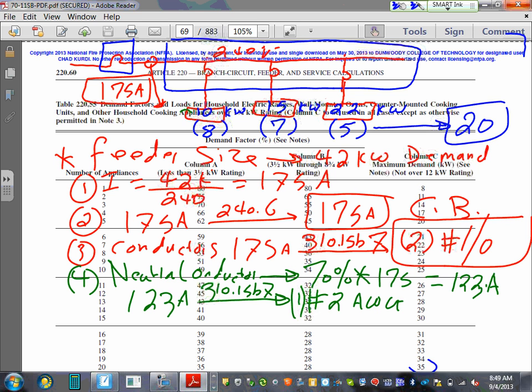Now we're going to go down here and we say, here's our size. My size is going to be 2 conductors, 1 aught, and 1 conductor, number 2. So that's the size of my service coming to my building. Size me a pipe now. What did we do yesterday? Size a pipe. Would you be able to size an EMT conduit for this system?